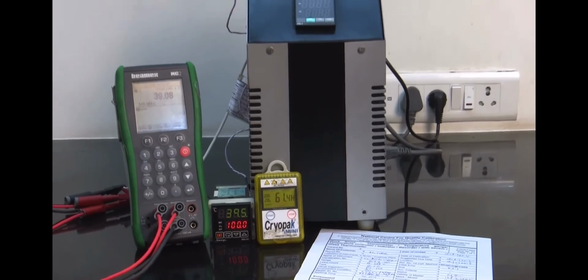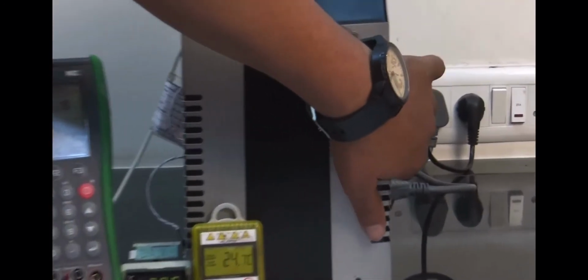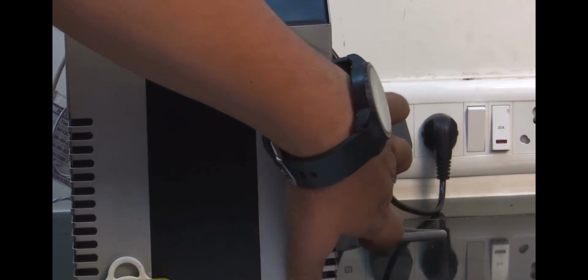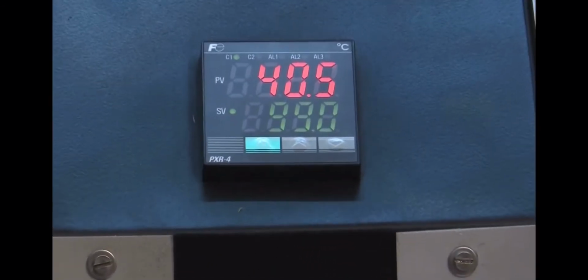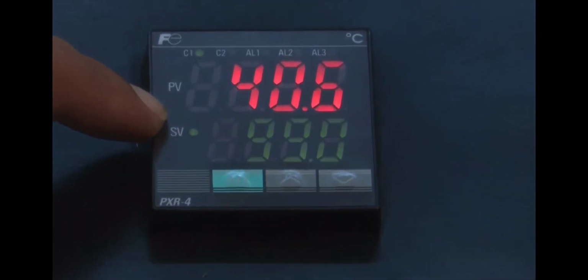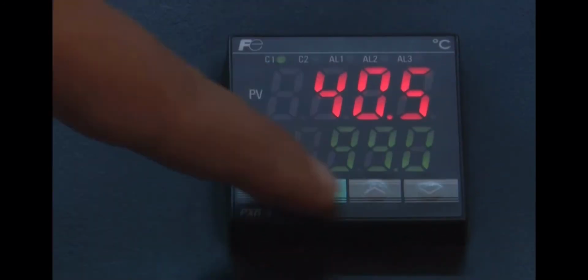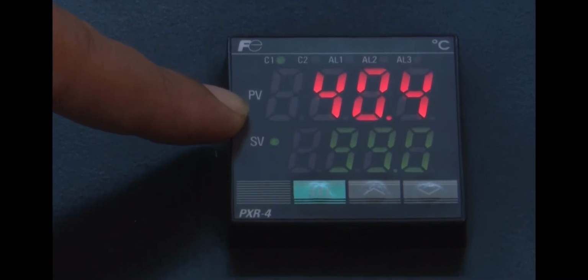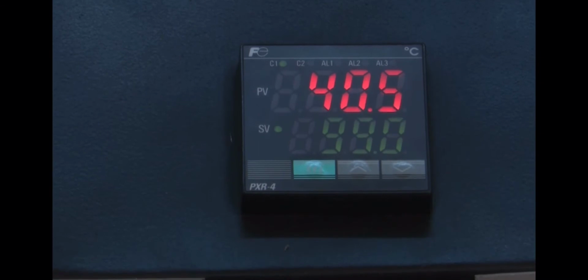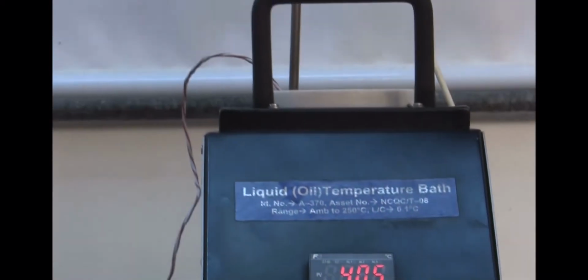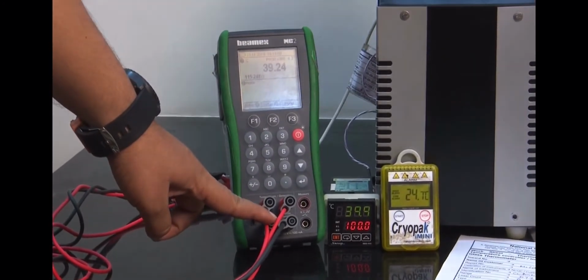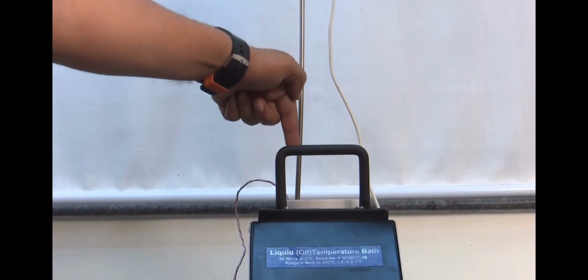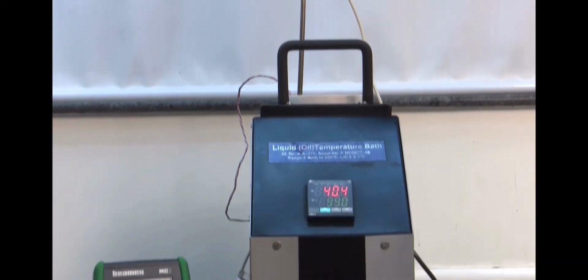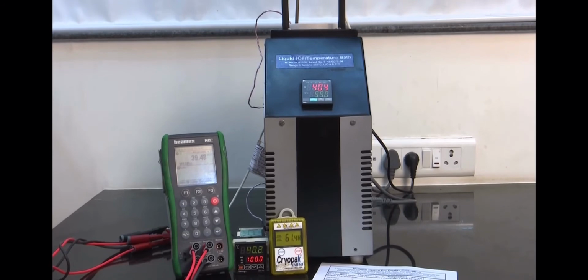First of all, connect the temperature bath to the electricity supply and switch on the power. Observe the display on the controller. It must show that the bath is ready to use. Check that master temperature sensor attached with multifunction calibrator and UUC are immersed at the same depth inside temperature bath. Now I am beginning calibration of this controller with sensor.